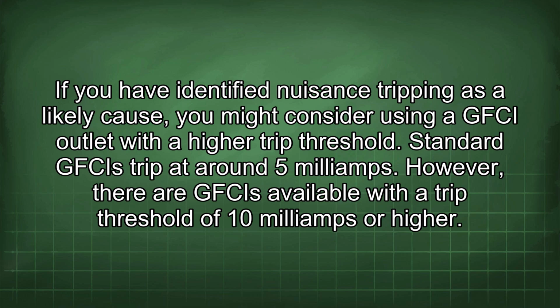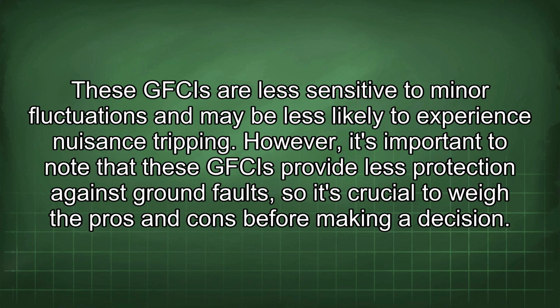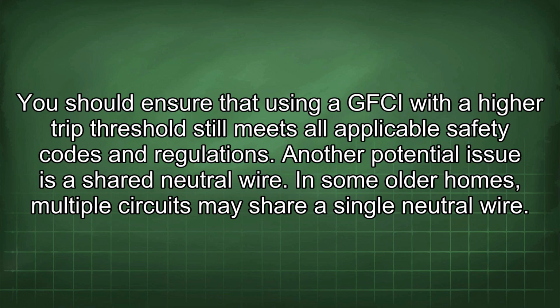If you have identified nuisance tripping as a likely cause, you might consider using a GFCI outlet with a higher trip threshold. Standard GFCIs trip at around 5 mA. However, there are GFCIs available with a trip threshold of 10 mA or higher. These GFCIs are less sensitive to minor fluctuations and may be less likely to experience nuisance tripping. However, it's important to note that these GFCIs provide less protection against ground faults, so it's crucial to weigh the pros and cons before making a decision. You should ensure that using a GFCI with a higher trip threshold still meets all applicable safety codes and regulations.